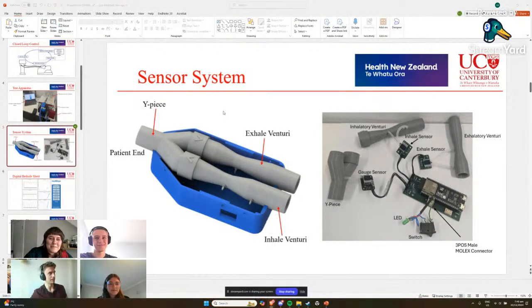We've just got a picture of it with the lid off. At the patient end, you've got a Y piece splitting the flow into the inhalatory and exhalatory side, and inside those bands we've got little one-way valves, which we adapted and made internal, slotting inside the venturi and the Y piece. That prevents flow from going the wrong way when breathing, so you get all the inhalatory pressure through the inhalatory sensors and exhalatory through the exhalatory venturi, giving the right flow measurements. We can see the sensors here, all differential pressure sensors, but the one at the Y piece is vented to atmosphere, so it measures gauge pressure. That's all connected to an ESP32 board running Bluetooth, connecting to the computer and ventilator.